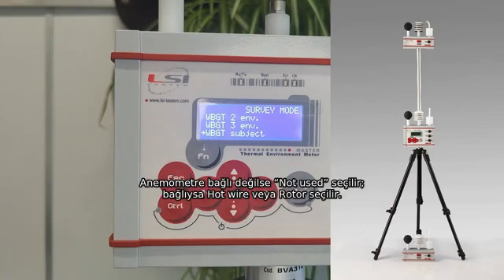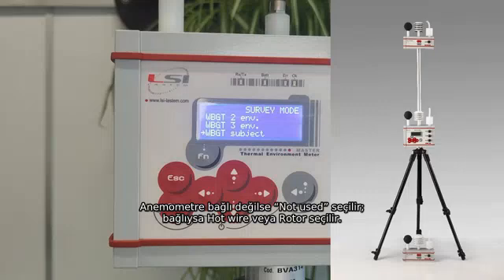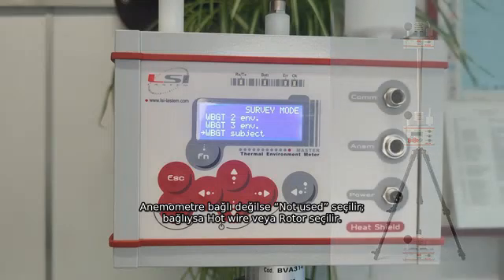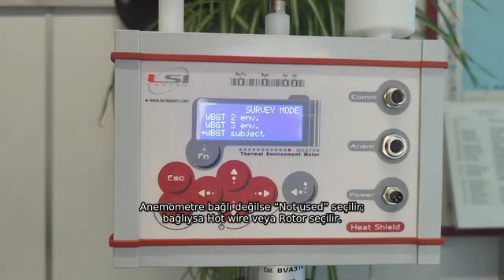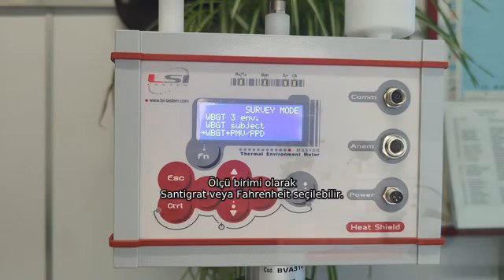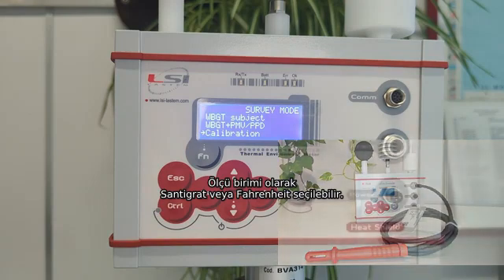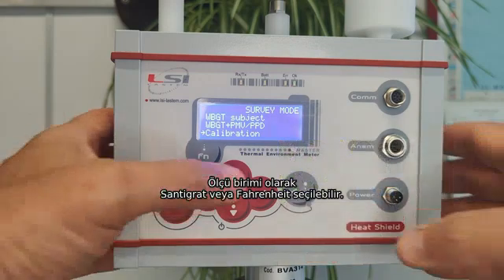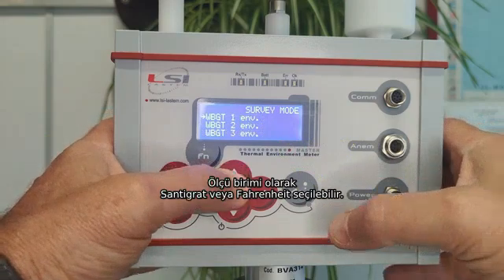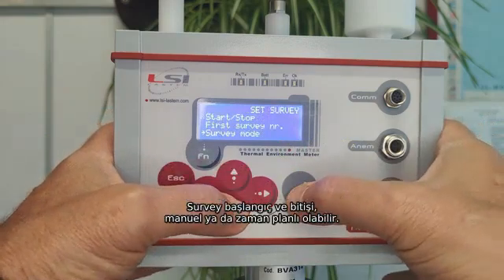Even in this case satellite units are needed, and mounted on the same vertical. This is if we need to perform WBGT and PMV-PPD assessment at the same time. Calibration, if we need to perform a calibration session using the verification probe. When the survey mode has been selected, we need to enter some parameters related to the subject.